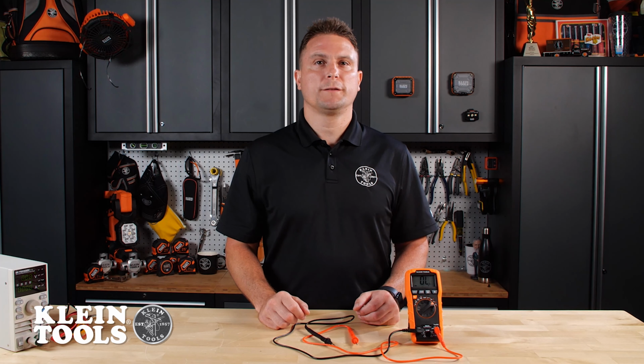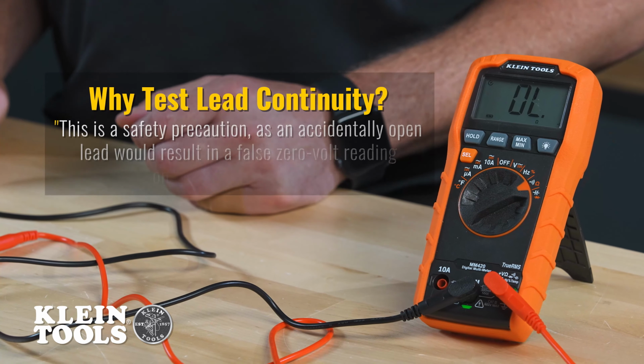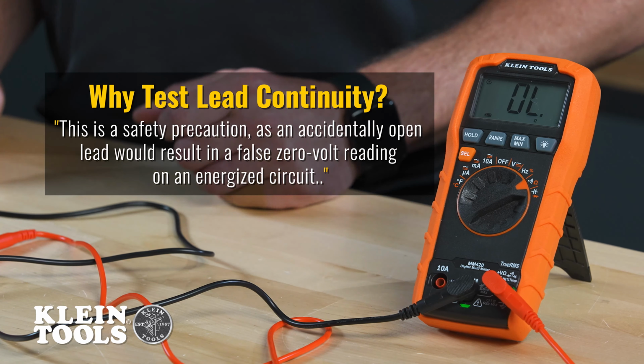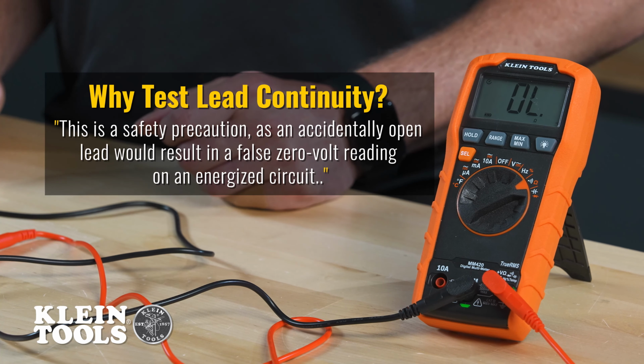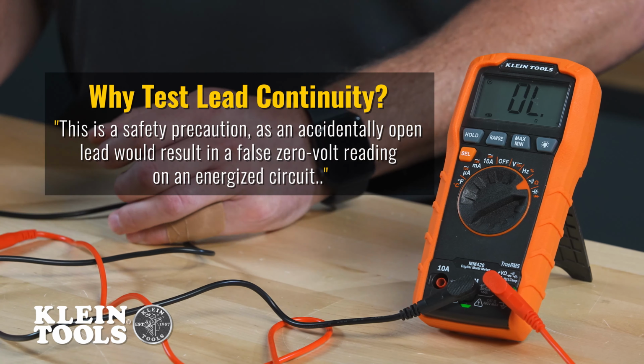Before you use any multimeter, you should always confirm the test lead continuity. This is a safety precaution, as an accidentally open lead would result in a false 0 volt reading on an energized circuit. Here's how to check lead continuity.